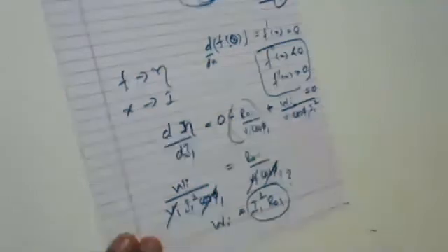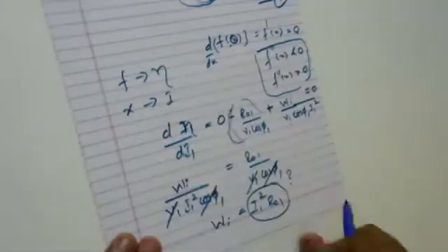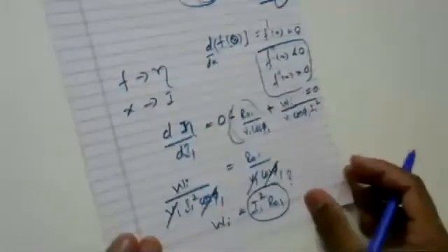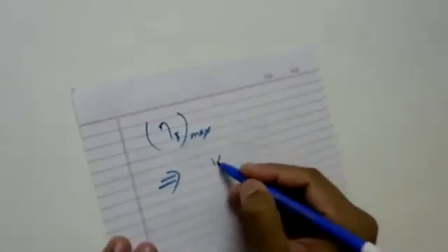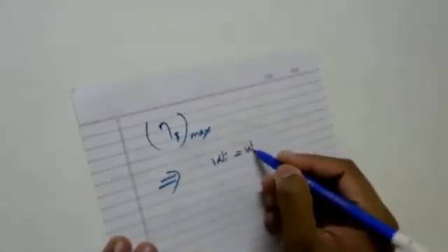Good, Mary. This I1 square R01 is nothing but the copper loss. So this equation is saying that the efficiency of a transformer can be maximum, I can achieve the maximum value of efficiency of my transformer, only if iron loss is equal to the copper loss.